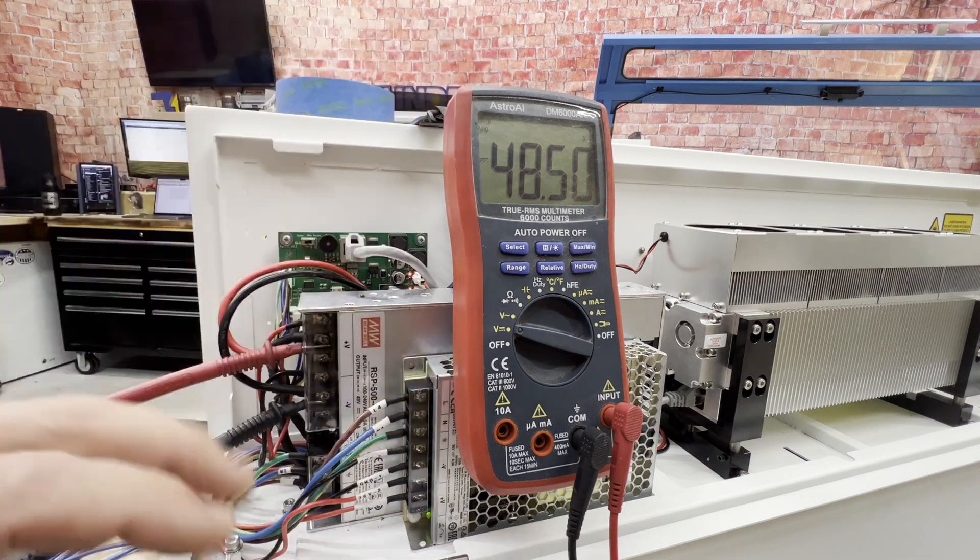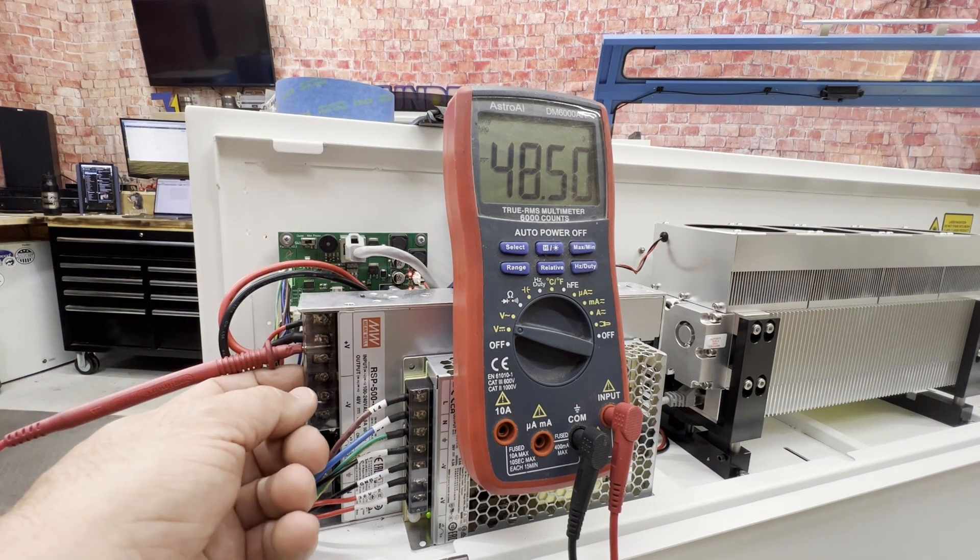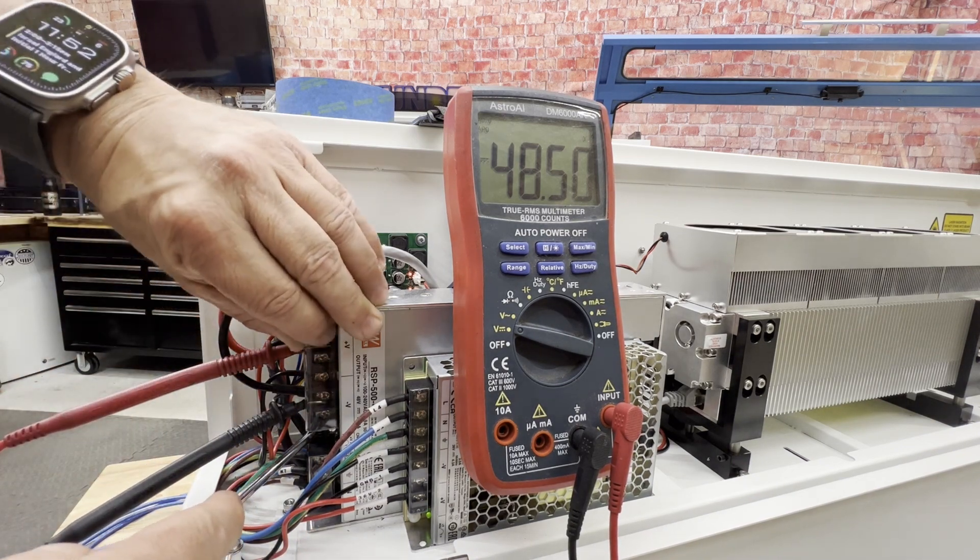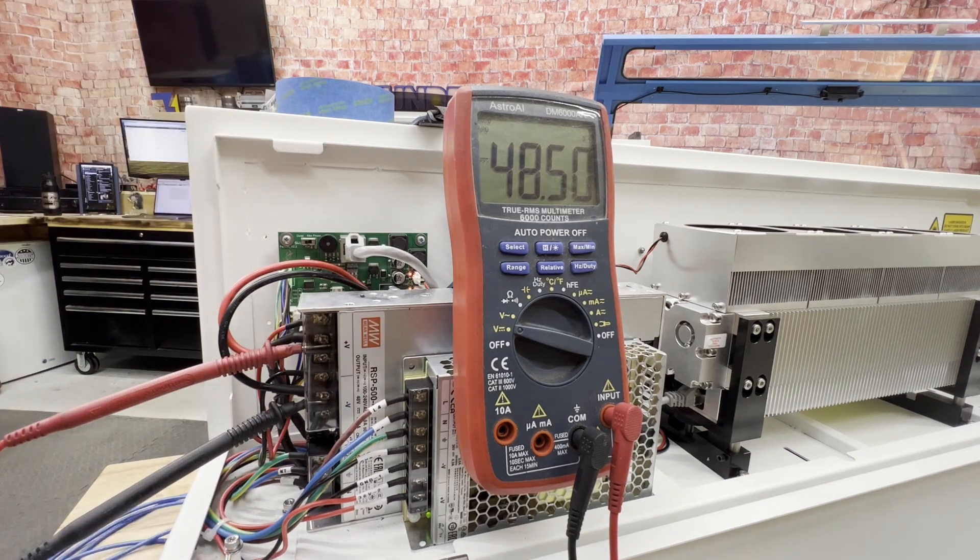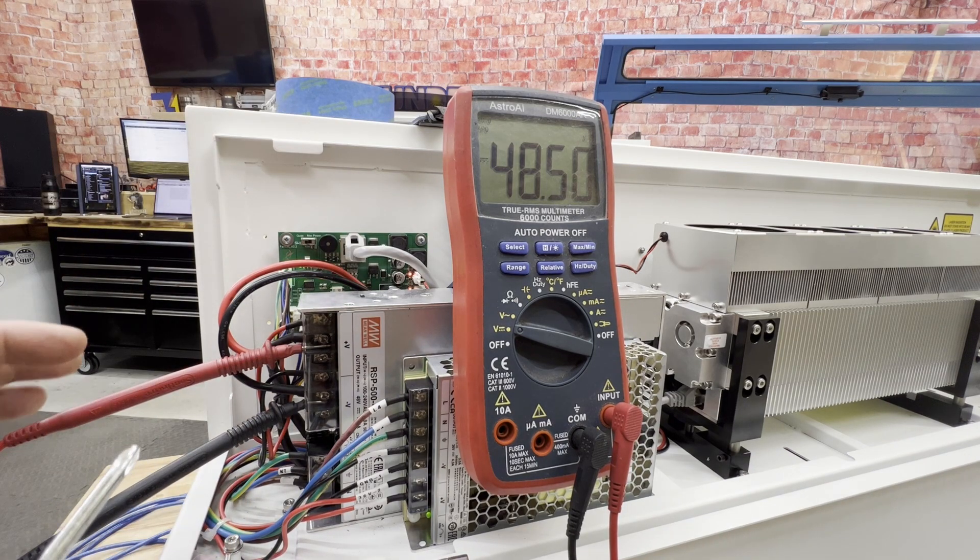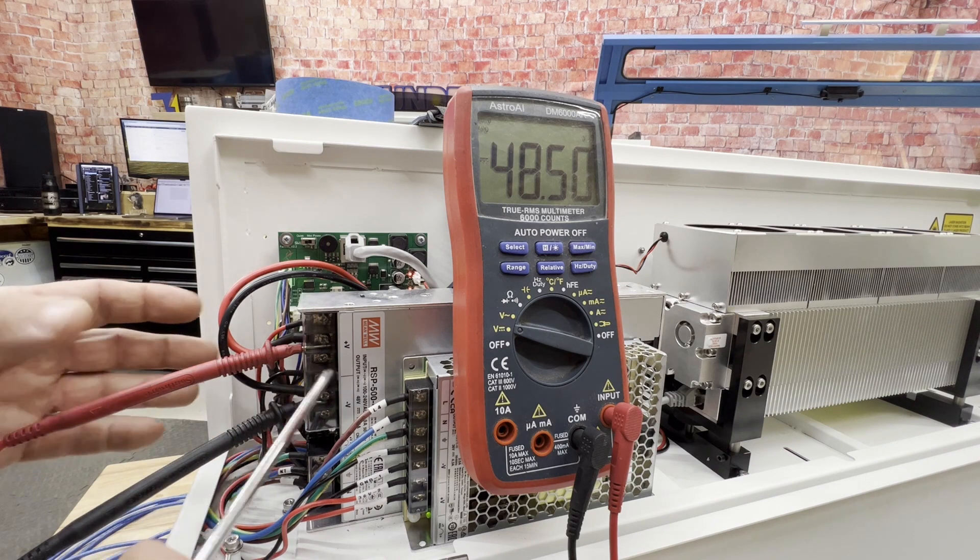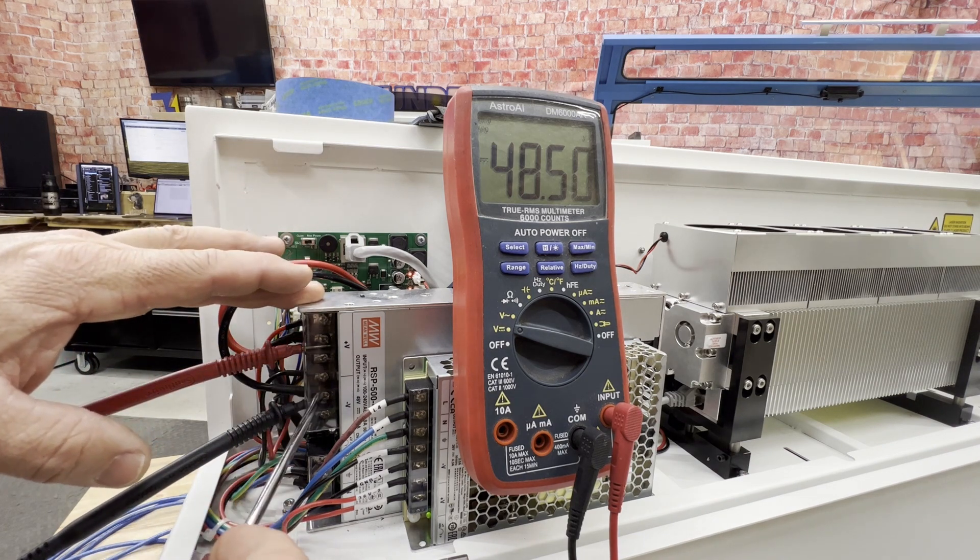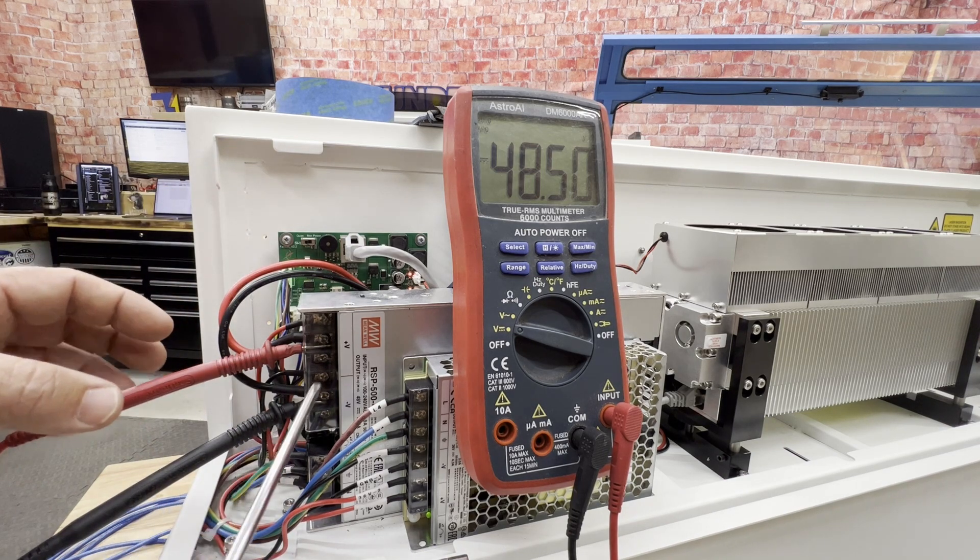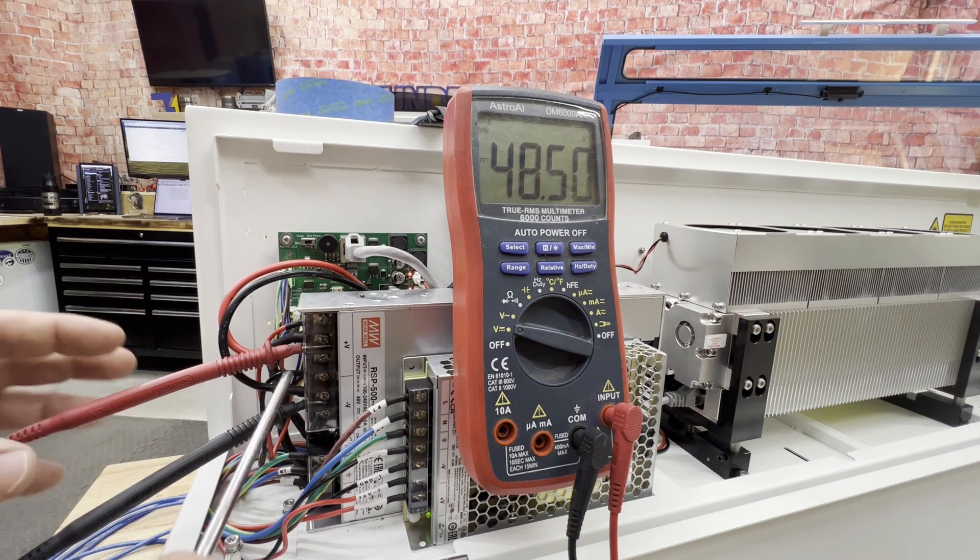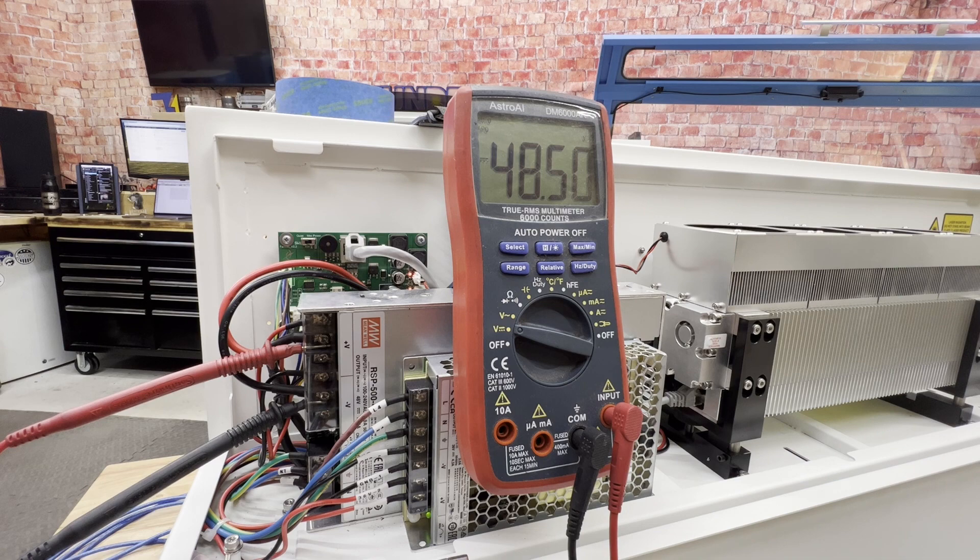And that really covers it as far as the 48 volt power supply and adjusting your DC current going to the tube. That's how we do it. One thing I do want to note is if you are having difficulty, there is a little clear plastic cover here. I recommend trying to do everything with that on, but if you're having difficulty you can remove that cover, access the Phillips head screws that hold these positive and negative terminals, and use that screw to hold your probes in.